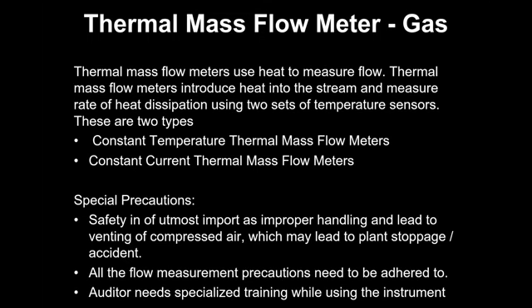that is again a very small pressure, so it doesn't matter. But a compressor is operating at 7 kg, gas can be at higher pressure. So the thermal mass flow meter is insertion type. That makes it very complicated because at a 7 kg pressure pipeline, we need to insert the probe. Now for inserting, there is a provision, there are two sets of valves and you can insert it without any accident, but there are chances of accident happening.